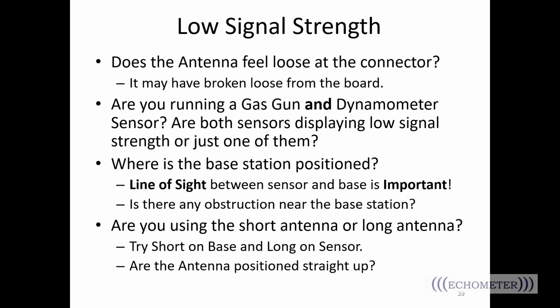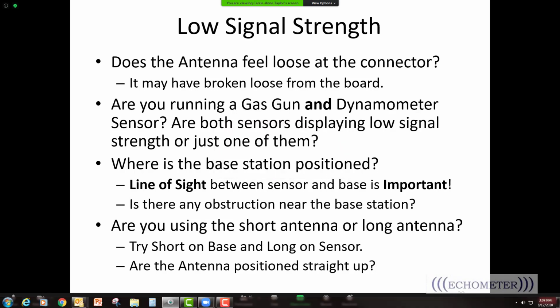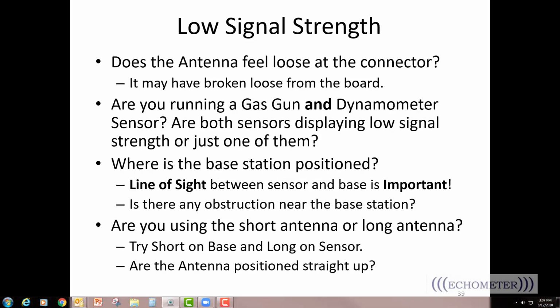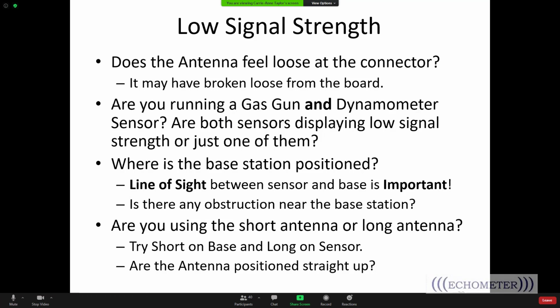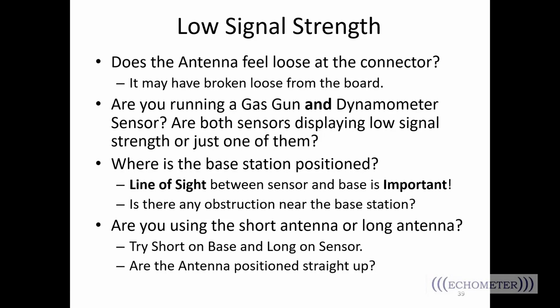When I say location problem, if you're in an area where you've got a SCADA system or you see the big antennas and things like that, if you've got a lot of signal interference, then that's going to affect the signal strength that you have between your sensors and your base station. So where is your base station positioned? The line of sight between the sensor and the base station is extremely important. So you want to make sure that there's no obstructions near the base station or between the sensors and the base station. A lot of people have the base station just sitting on their dashboard. You can put Velcro, just stick your base station up there, and that's perfectly fine if you've got good line of sight. Make sure that there's nothing in the way.